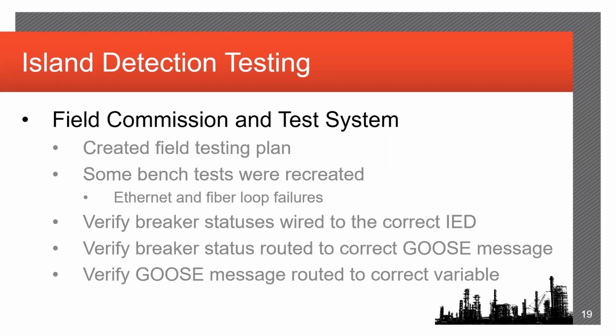Beyond that, the vast majority of the time in the field was spent verifying that the breaker statuses were wired to the correct IED, that the breaker status from that IED was routed to the correct GOOSE message, and that the GOOSE message was routed to the correct variable inside of the logic processor. The way we did that is literally one breaker at a time: open breaker number 1, and then follow it all the way from the IED to the GOOSE message to the logic processor, and verify that it was showing up in the right spot. Which with 17 breakers is not that difficult, but of course everything you do in an oil refinery always takes longer than you think it should.